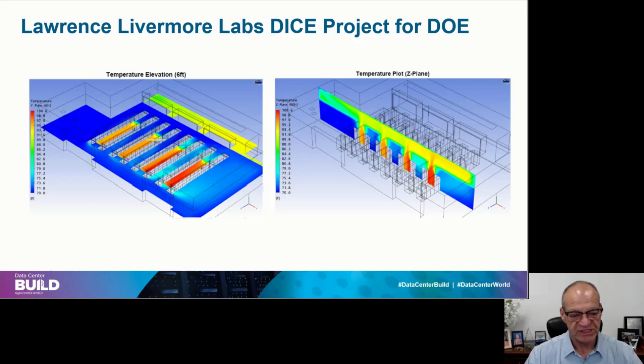This shows that the racks could be cooled at load. It's one of many slides showing, at a 6-foot elevation, where the heat is contained and rejecting. Yes, these are air conditioners going back, external to the building. They're not exactly what you saw in the other picture, but it's the same concept with a different manufacturer. This is one we had built prior.